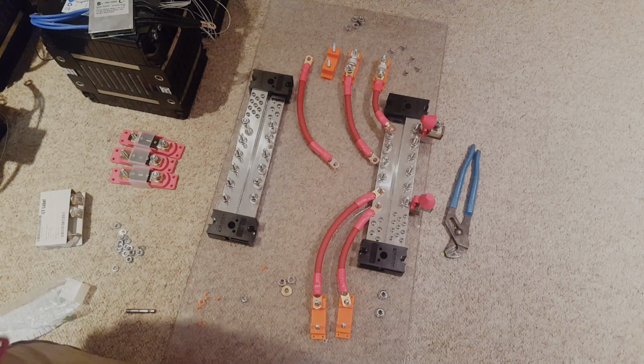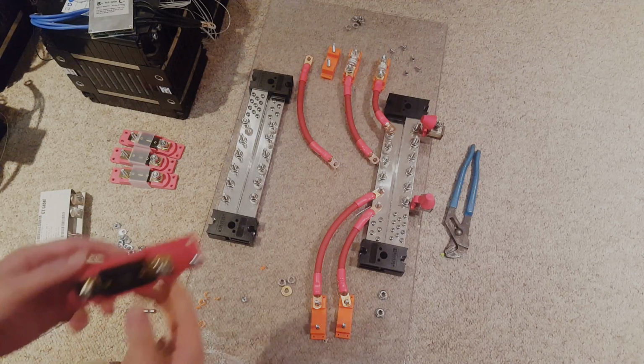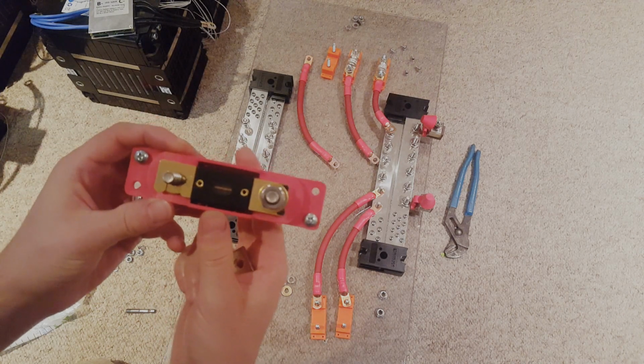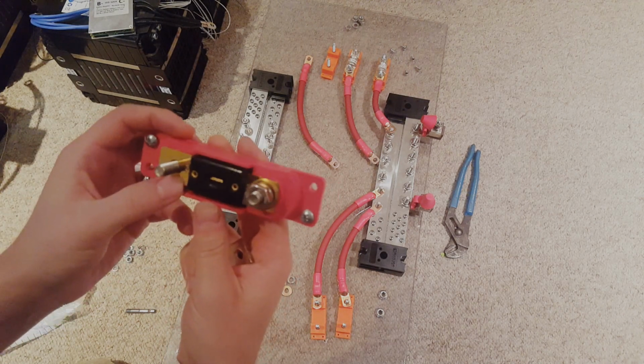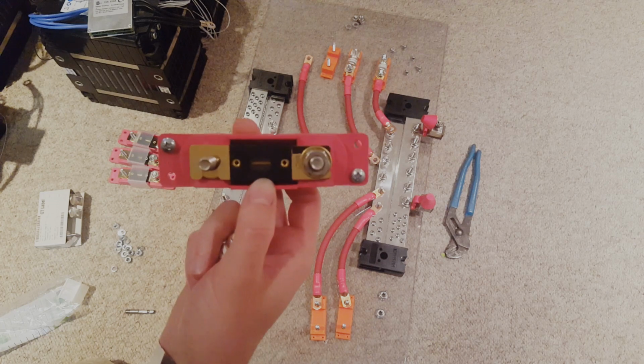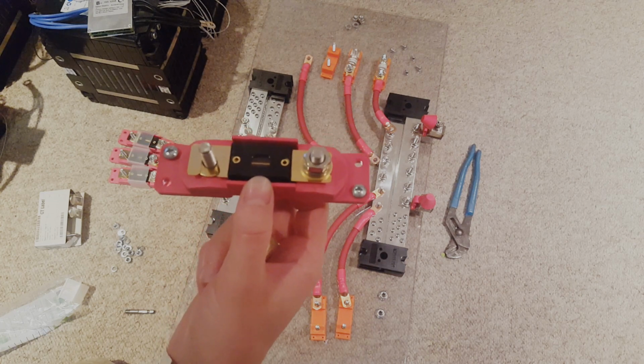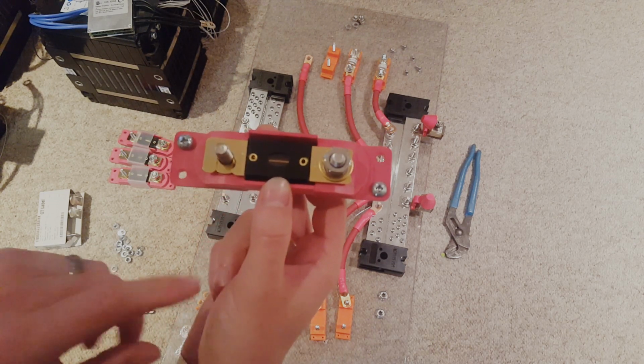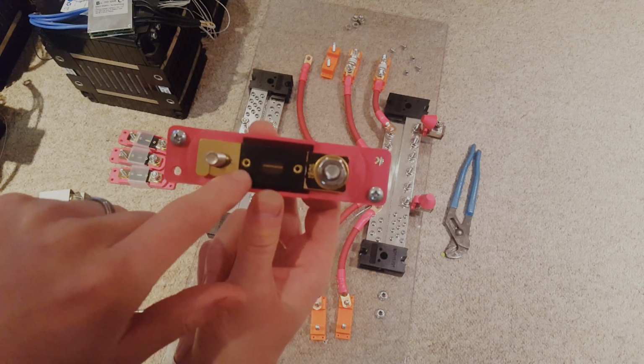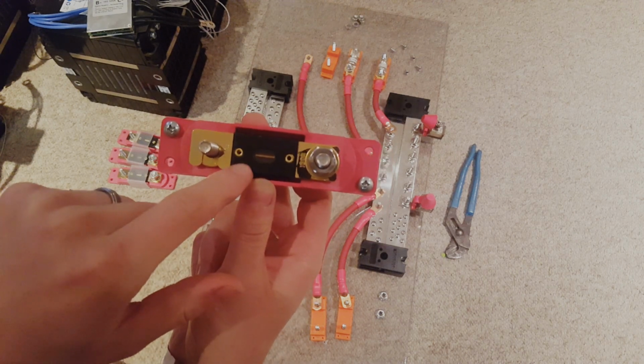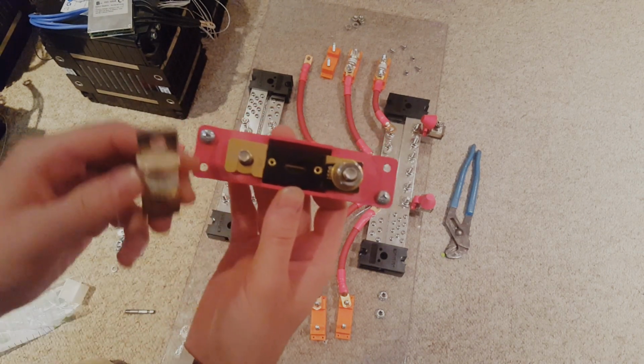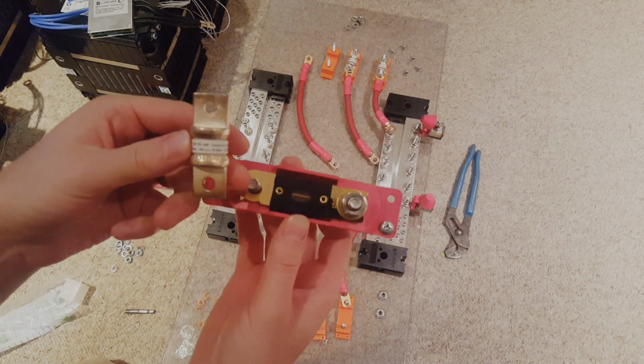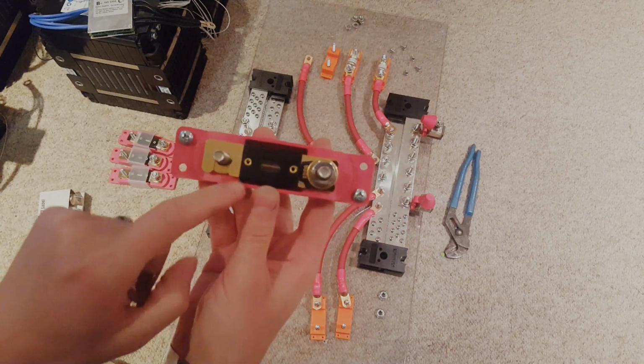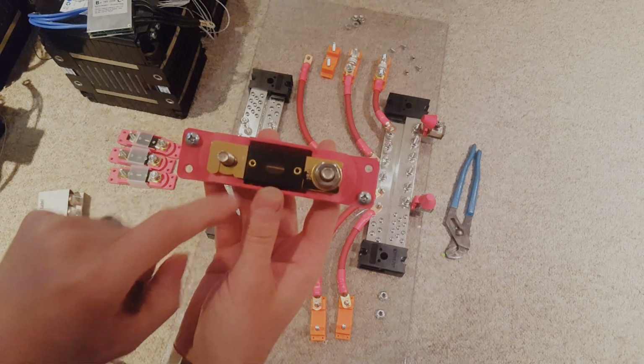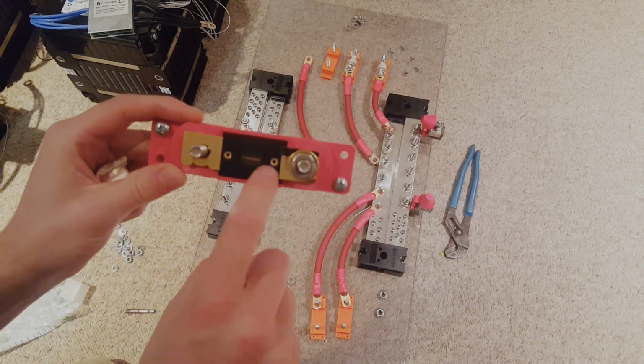All right, so before we go any further, I had a bit of a hiccup. I overlooked something about these fuses. These are ANL fuses. So these are actually rated to 32 volts, not 48 like I originally thought. But the bigger problem is this fuse design is not rated for high current interruption, whereas a Class T fuse like this is. So what can happen is if you have a short circuit on one of these batteries, this will actually arc across here.